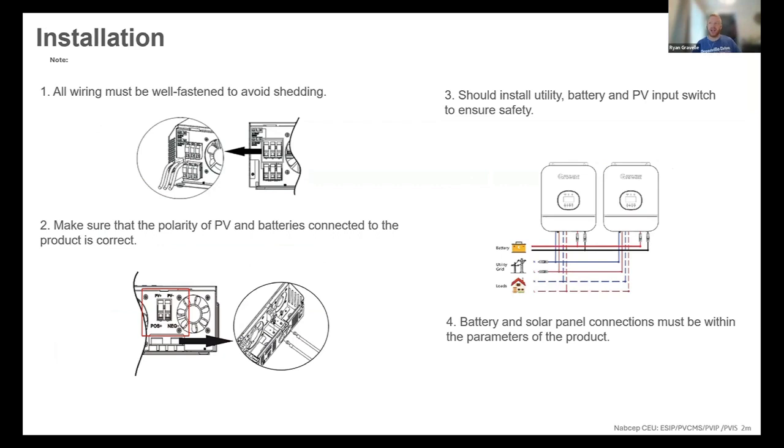That said, one thing that has come up in some markets with AHJs is depending on the inspector, sometimes they do want rigid conduit or troughs underneath the SPF units. We have seen that feedback, and we've actually seen a lot of success with running these right adjacent to electrical troughs. So again, depending on your local inspector, you may want to discuss that with them during application, but I'll show how that compares to the MIN series product in a moment. Where we have built-in knockouts and a terminal box built right into the inverter.